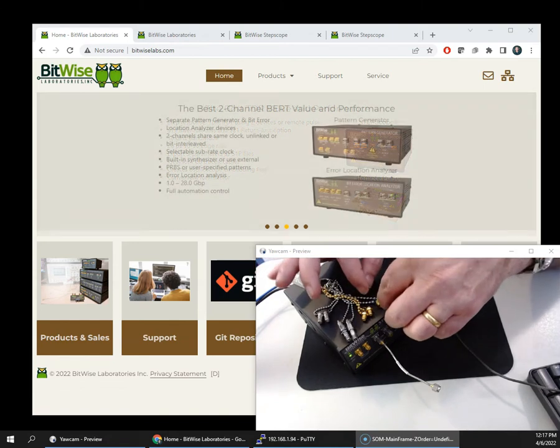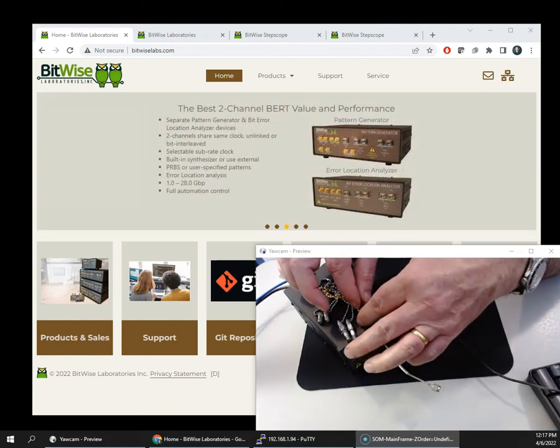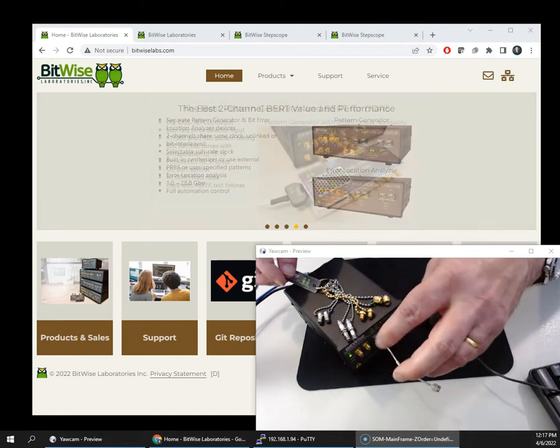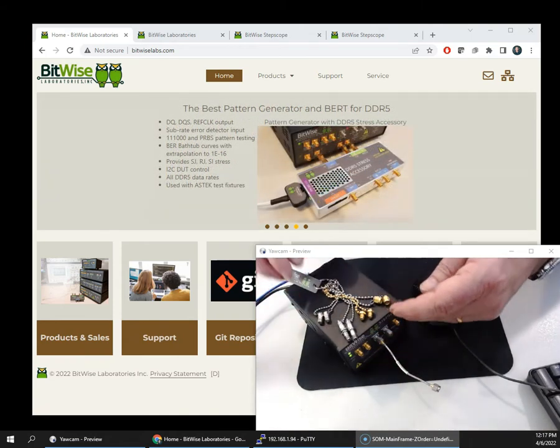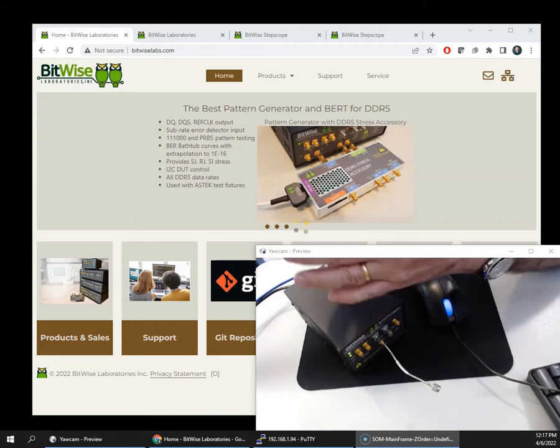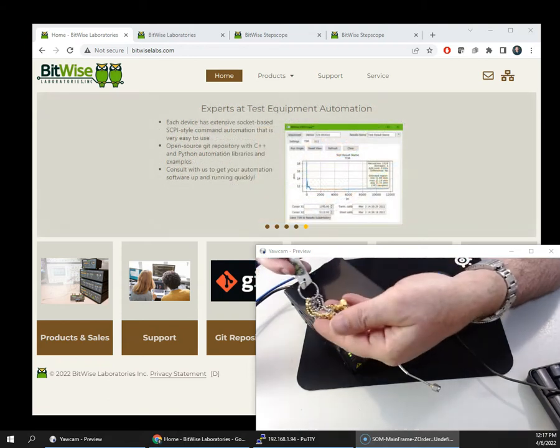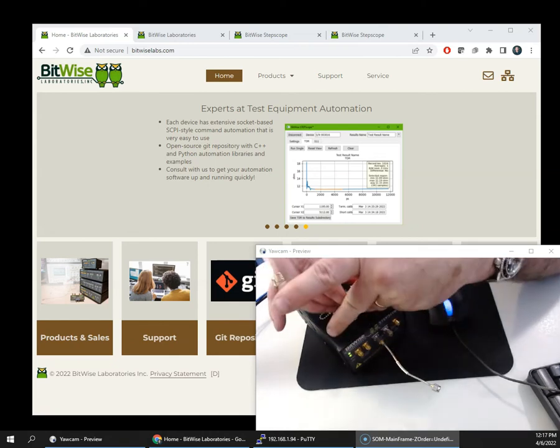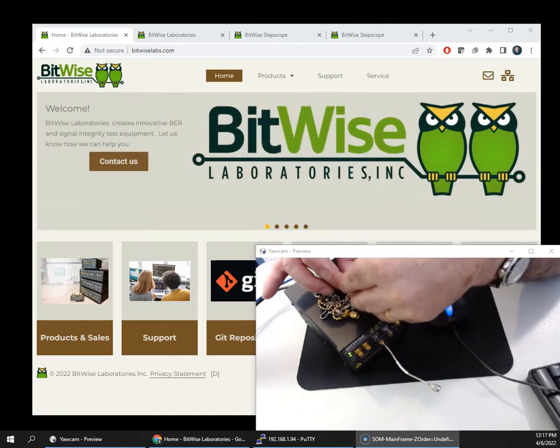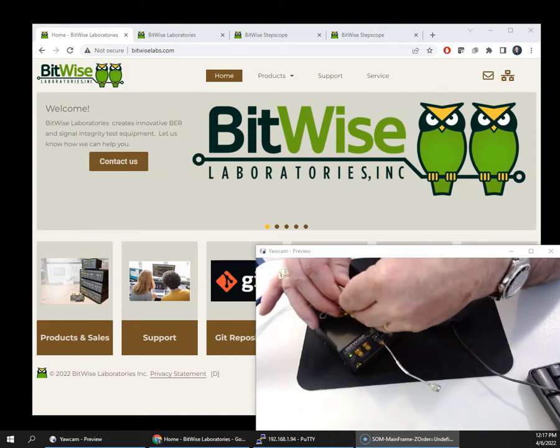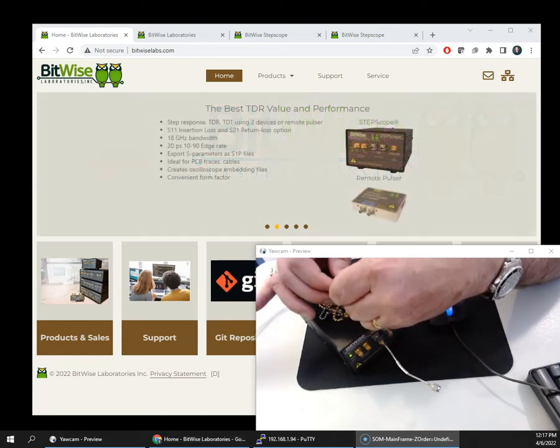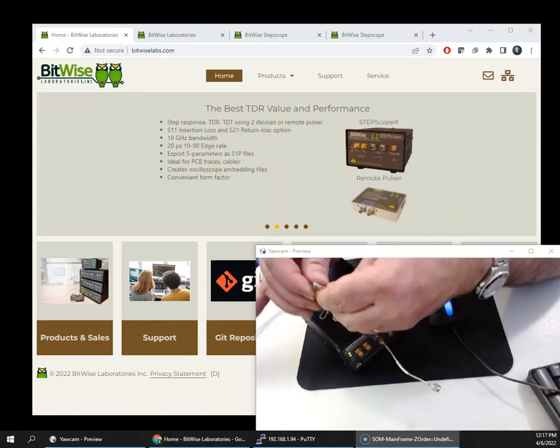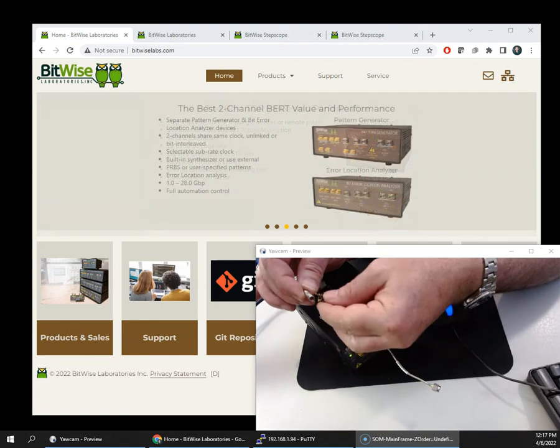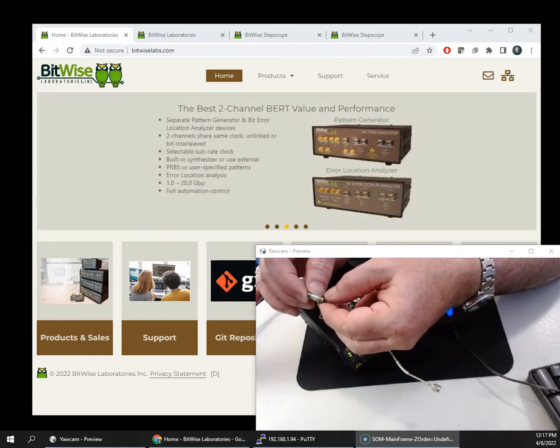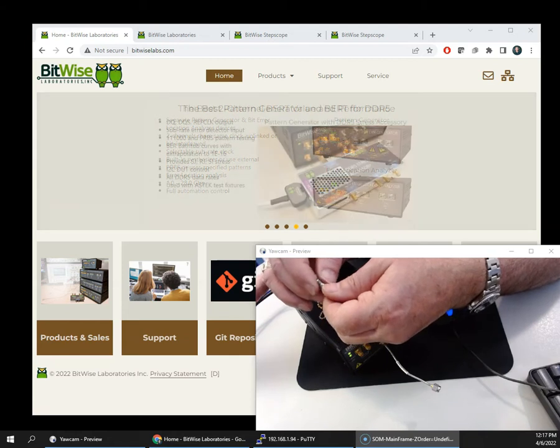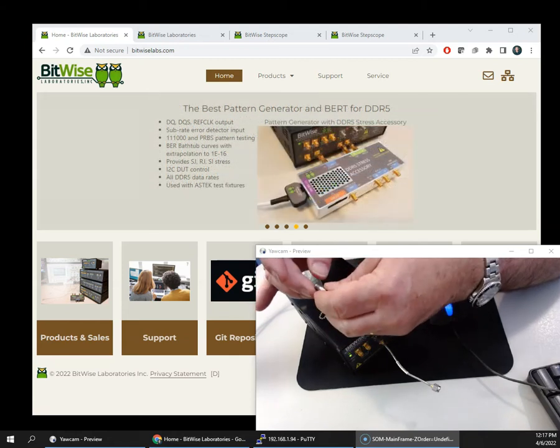But these are very high-end terminations that come on chain links so that we can keep track of them, and it's a complete set differential. So that with this one kit, you can easily keep track of all the terminations you need to be able to make measurements. In addition to two male and female shorts and terminations, there's also a set of very nice through 2.92 millimeter through connections that are used here too. This is for those people doing transmission measurements, where you have to go through a device.